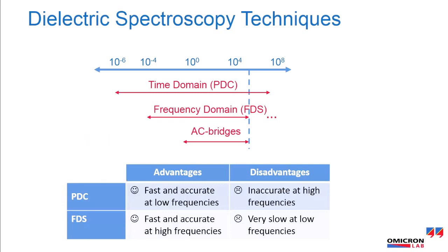There are advantages and disadvantages of these two dielectric techniques. The PDC measurement method is fast and accurate at low frequencies but inaccurate at high frequencies. The FDS measurement method is fast and accurate at high frequencies but very slow at low frequencies.